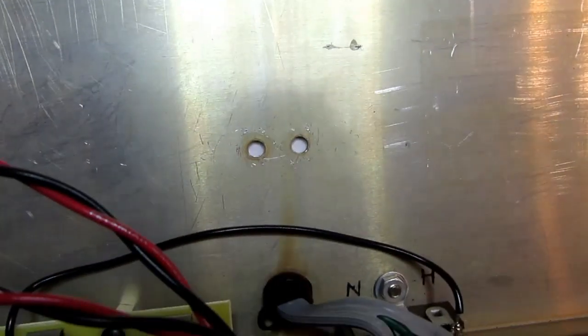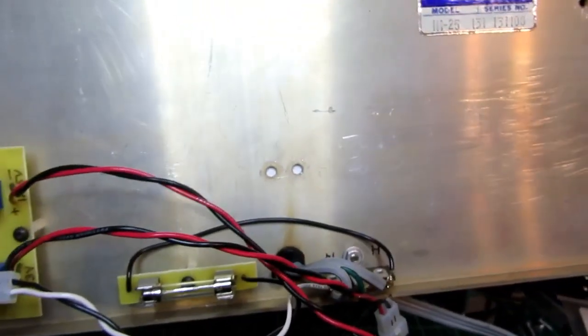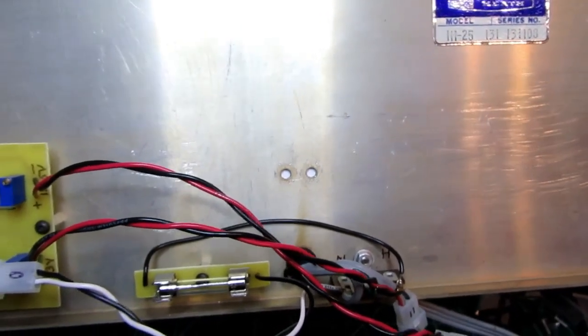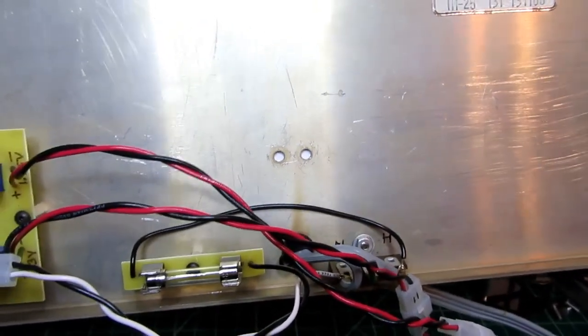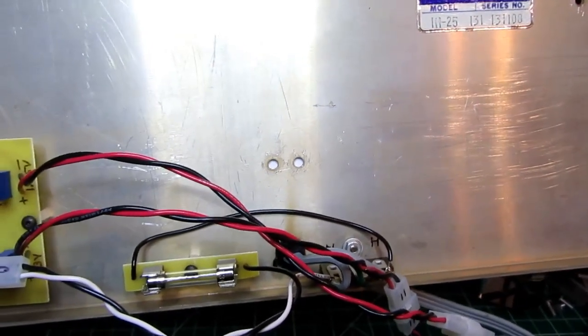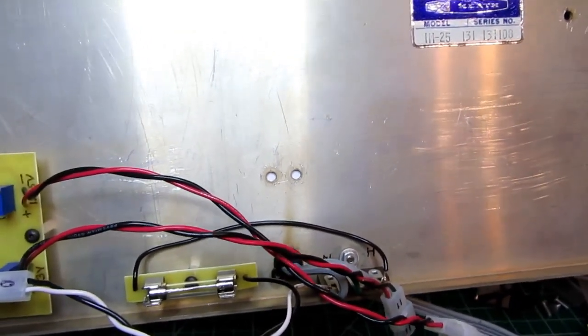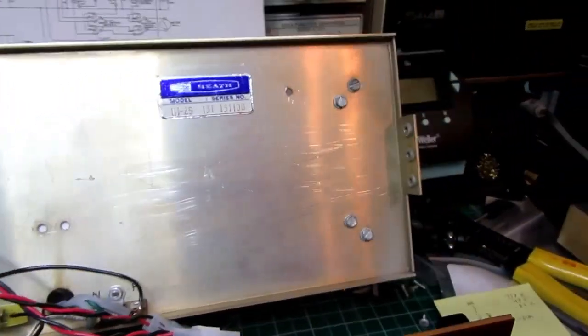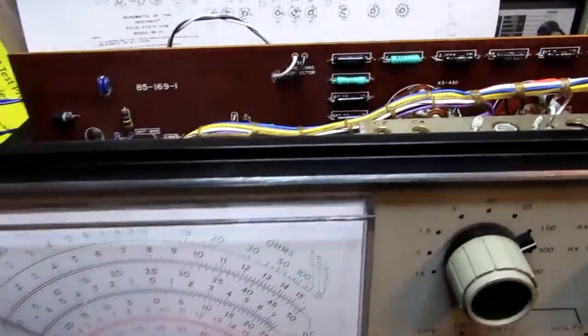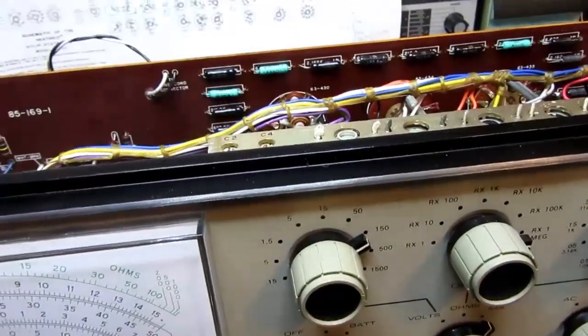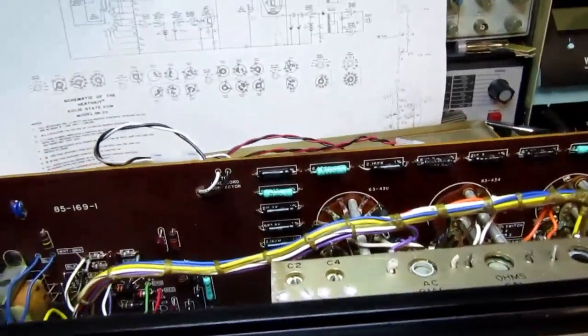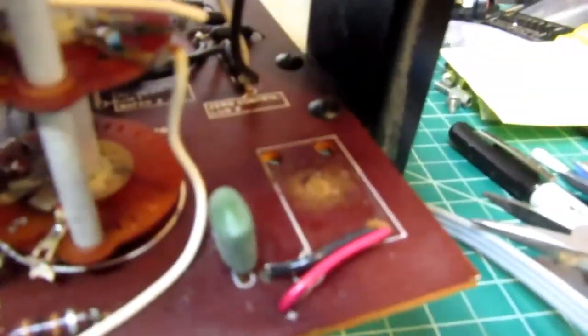And then bolted on right here where those 2 holes are, there's a similar holder, but it only holds 2 C cells for a total of 3 volts. And that provides the excitation voltage for the ohm meter circuit. In other words, it provides the current that goes out through the resistor under test. In addition to those batteries, the main battery provides power for the actual active meter circuit. The front end doesn't use any power except for a tiny amount used by the AC converter that converts AC to DC.